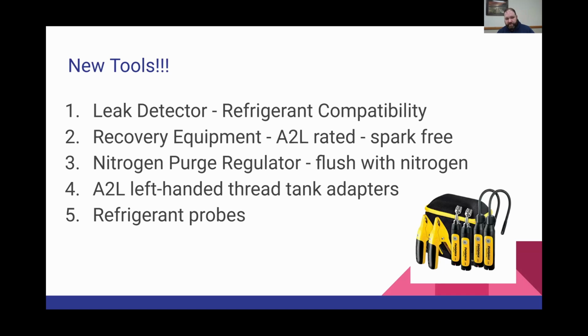Number one is we need to make sure that if we're working on these systems, we have a leak detector that's capable of detecting it. So just making sure we have some compatibility there. There is a recommendation that your recovery equipment, so your recovery machine, is rated for an A2L, meaning it's spark free. The other thing is the nitrogen purge regulator. Best practice has always been to purge with nitrogen so that we keep our system as dry as possible. It's just a little bit more important now that we have these A2Ls.